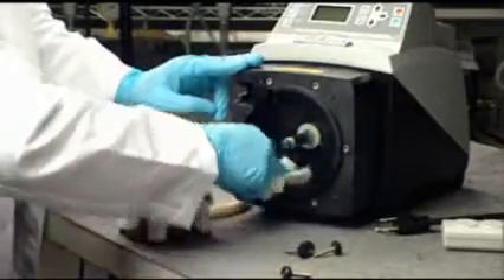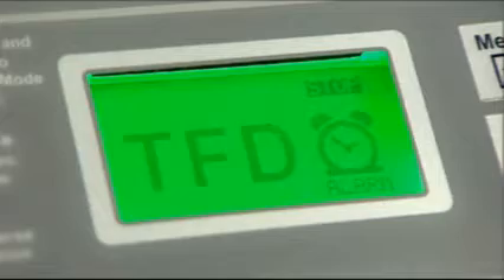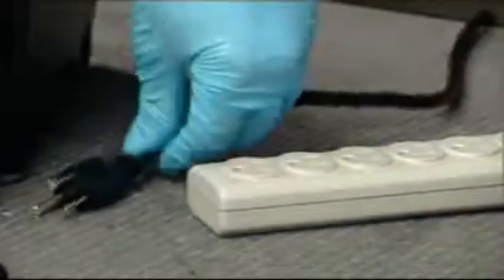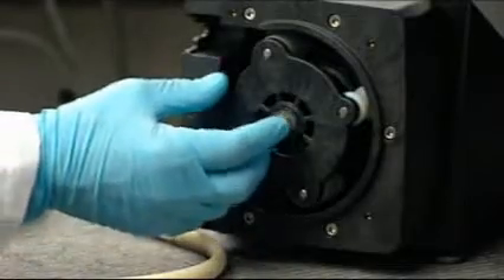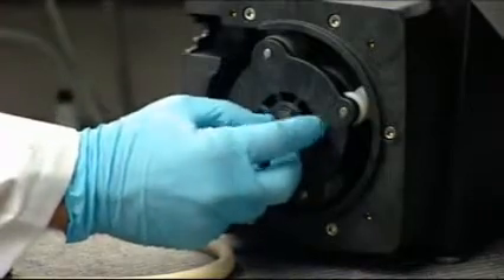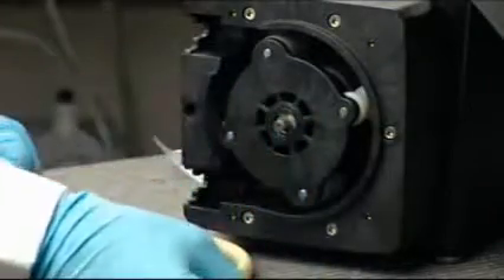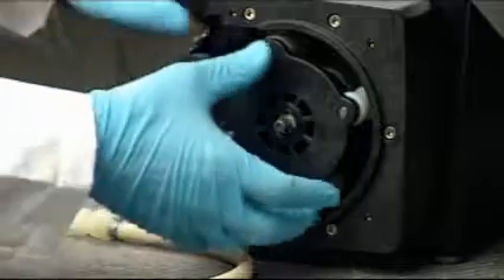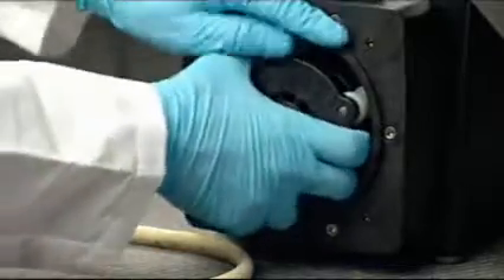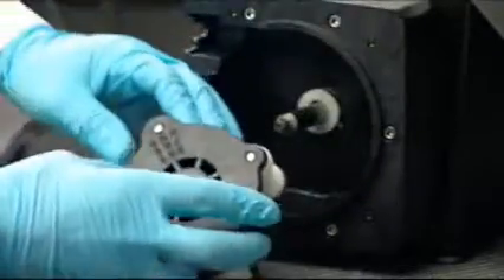The roller assembly and pump head should be inspected and cleaned before installing a new pump tube. This is especially important if the pump tube ruptured and the TFD system was activated. Be sure to also wipe clean the sensor pins. To remove the roller assembly, disconnect power to the pump. Remove the small spacer washer from the motor shaft. Remove the roller assembly from the pump head by pulling the assembly straight off of the motor shaft.